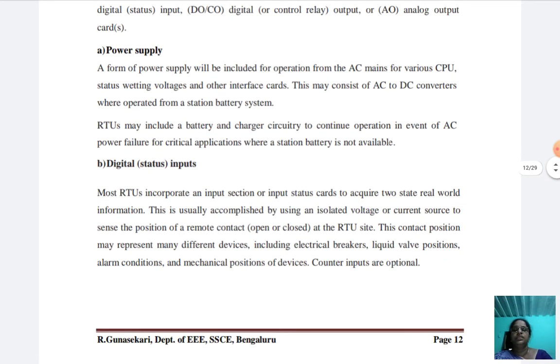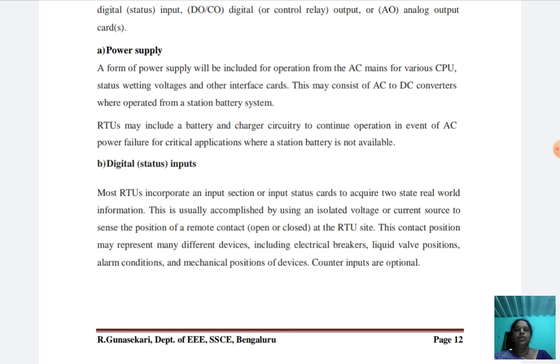The third component is digital inputs. Most RTUs incorporate an input section or input status cards to acquire two-state real-world information — that is, digital means either 0 or 1. This is usually accomplished by using an isolated voltage or current source to sense the position of a remote contact (open or closed) at the RTU site. This contact position may represent many different devices including electrical breakers, liquid valve positions, alarm conditions, and mechanical positions of devices. Counter inputs are optional.